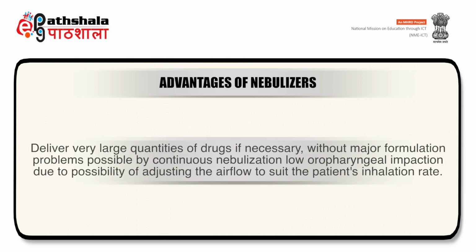Secondly, nebulizers deliver very large quantities of drugs if necessary without major formulation problems, possible by continuous nebulization, and have low oropharyngeal impaction due to the possibility of adjusting the airflow to suit the patient's inhalation rate.